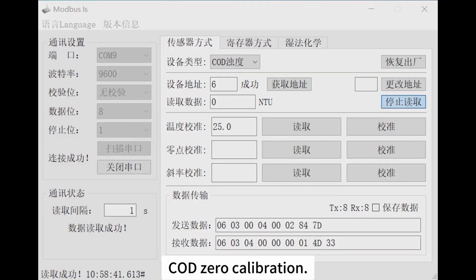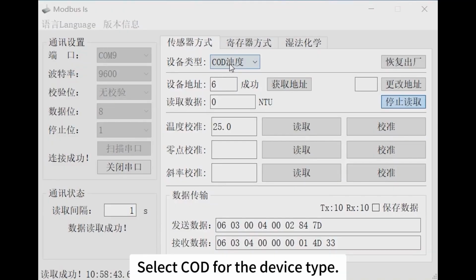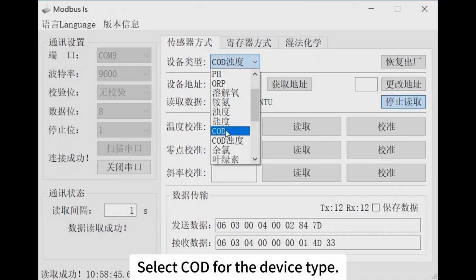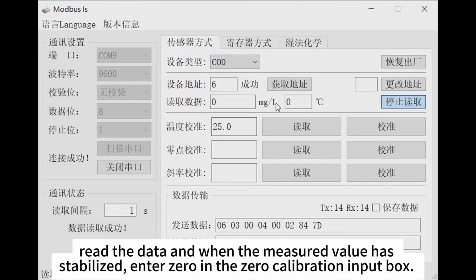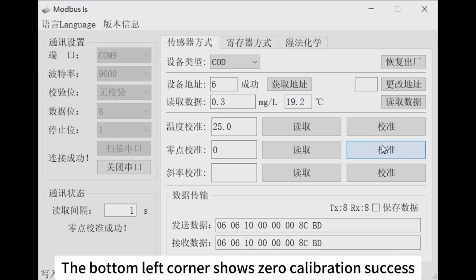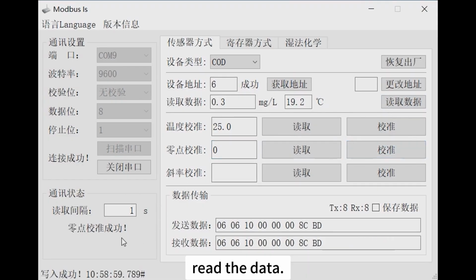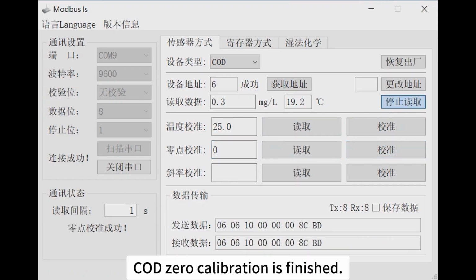COD 0 calibration. Select COD for the device type. Read the data, and when the measured value has stabilized, enter 0 in the 0 calibration input box. Click Calibrate. The bottom left corner shows 0 calibration success. Read the data. COD 0 calibration is finished.